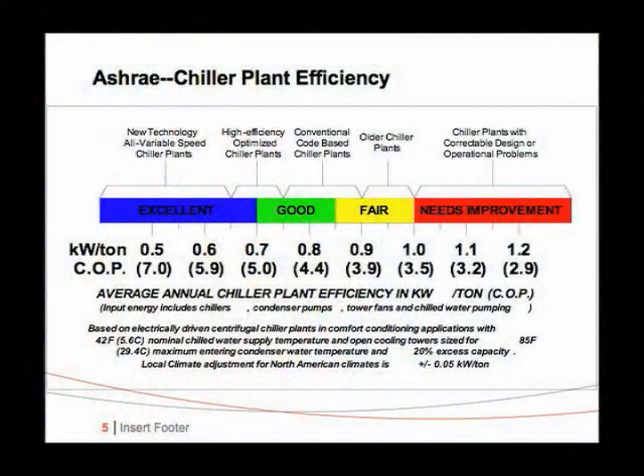You might be familiar with this from ASHRAE. This is a little bit loaded because it has seasonal temperature changes. But we would say 0.6 is okay, pretty good. 0.55 might be the current state of the art for comfort applications. And many audits in Singapore, which are sponsored by the government, I believe they have 140 audits now, show worse than 1.2. So there's a no-brainer method to get half the savings in HVAC. But you would not believe how difficult it is to get people to specify 0.6. My brother-in-law is also an air conditioning contractor and he can't do it, therefore.